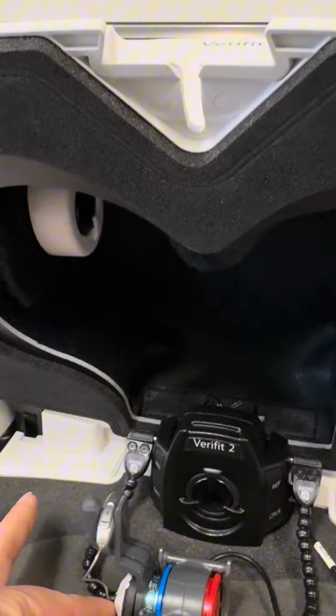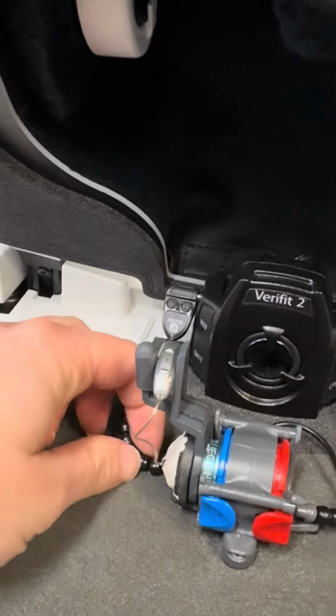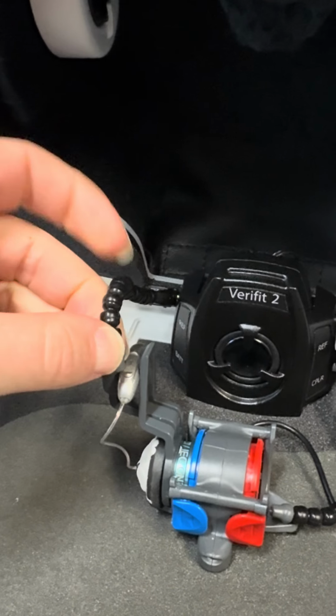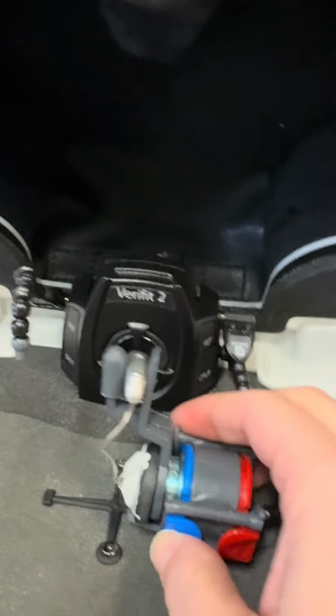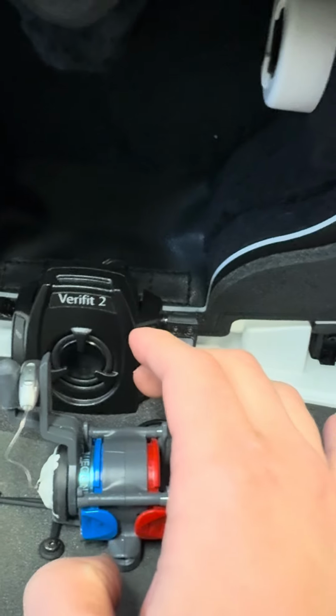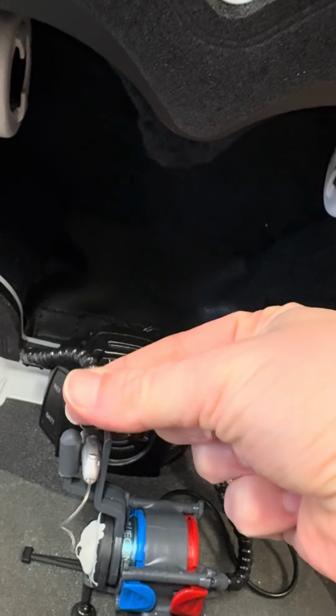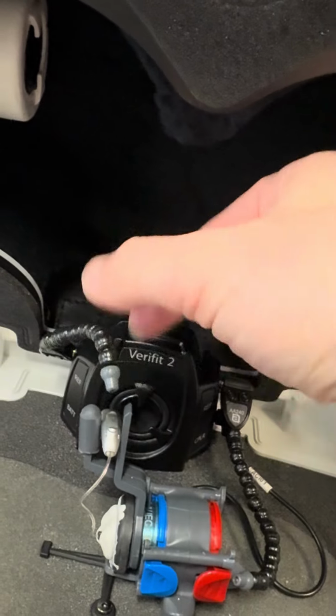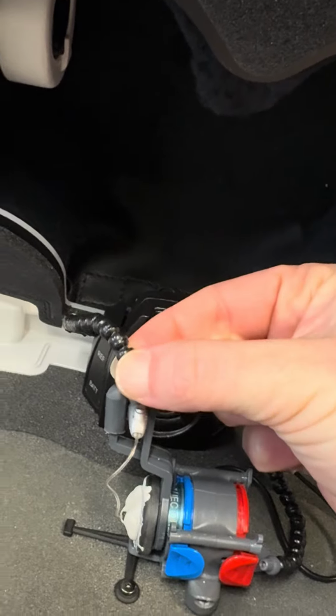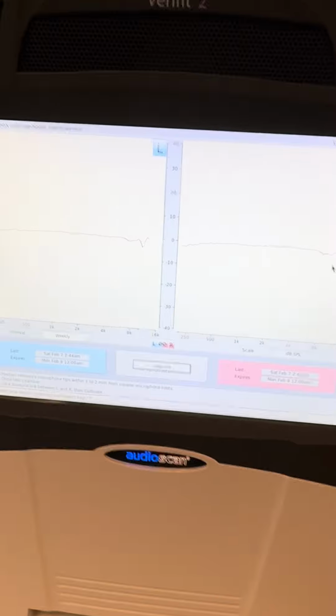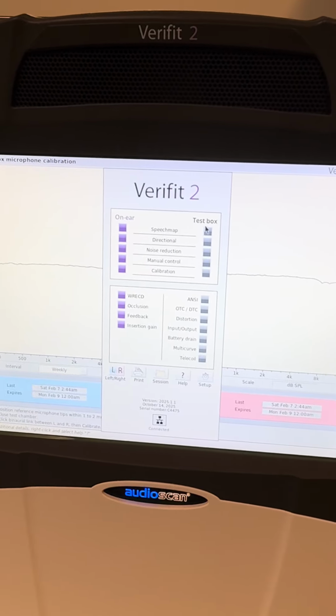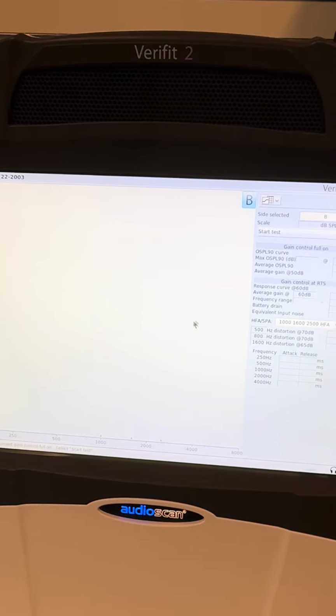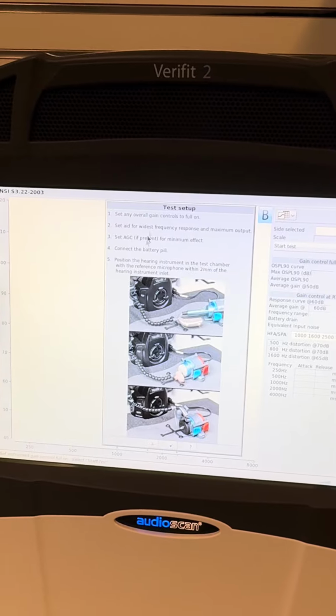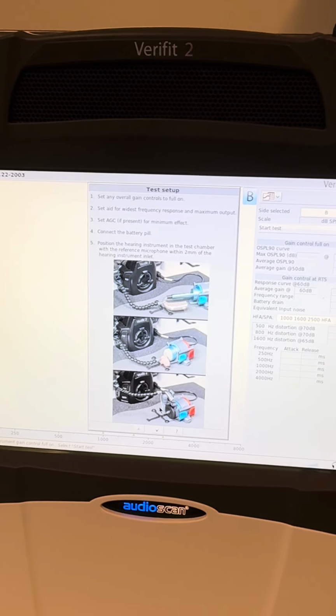Okay, to ensure you got a proper setup, you should not hear anything when the hearing aid is on full on gain, and we want to set the reference mic to hover over the hearing aid microphones. So we want to take it off this and put the hearing aids in line with this crossbar, and then position the reference mic about 1 to 2 millimeters away from the HA mics. And then we are going to shut and lock the test box, and then we are going to right click on the Verifit. Under test box we are clicking ANSI, and we just hit start test. It's just ensuring that we got it set up, see how it's over the crossbar and on the reference mic.